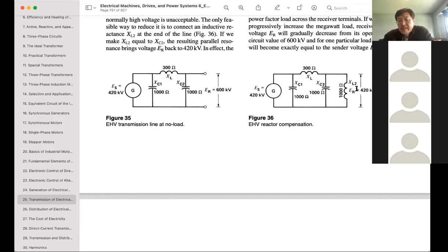So you need compensation. How much compensation do you need? This time, you need an inductor to compensate 1,000 ohm. Once you attach a 1,000 ohm inductor, the voltage drops to 400. That gives you an extreme example of extreme underload. There's zero load attached, so all your customers are cut off from the power. In that extreme example, the destination voltage became 600, dangerously above the 400. So you need extreme compensation, a 1,000 ohm inductor attached to it. With that compensation, your voltage will drop to 400 again.